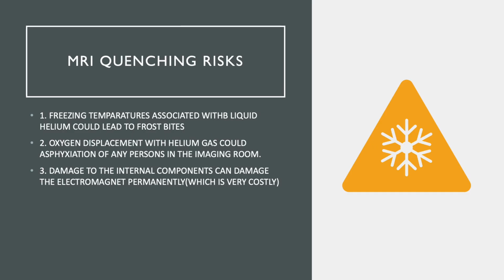There are certain risks that are associated with a quench, and the consequences can be extremely dangerous. First, freezing temperatures associated with liquid helium could cause frostbites, which can even cause death. And second, oxygen displacement with helium gas could potentially cause asphyxiation to any persons in the imaging room. Secondary to the risk of human injury is the innate risk to the MRI hardware itself. Once a quench begins, damage to the internal components and coils can damage the electromagnet permanently, and these can be very costly.